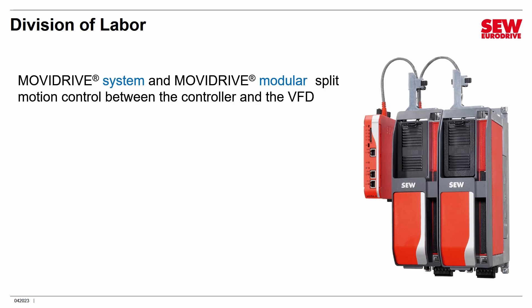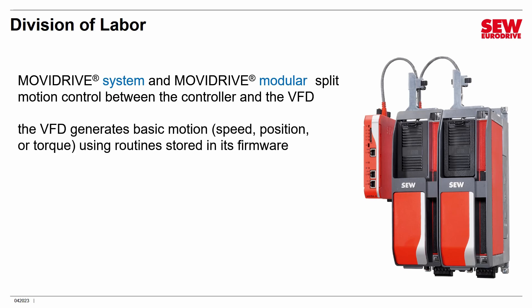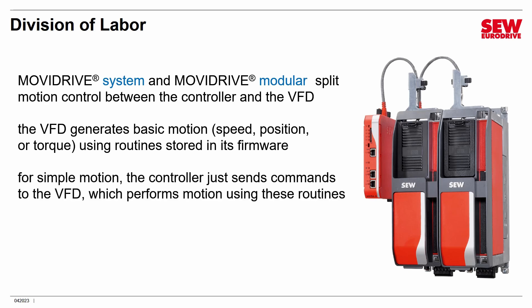The controller is doing the heavy lifting; the VFD is just doing some very simple things. For basic motion — speed, position, or torque control — you're just using those same routines stored in the Movidrive System or Movidrive Modular's firmware. What the controller does is send some basic commands saying, do these built-in firmware routines, and that's it. This is uninterpolated motion, and that doesn't put too much of a load on the controller. Those simple commands are invoking firmware routines — which we call Function Control Blocks, or FCBs — and that's really what we're here to talk about.